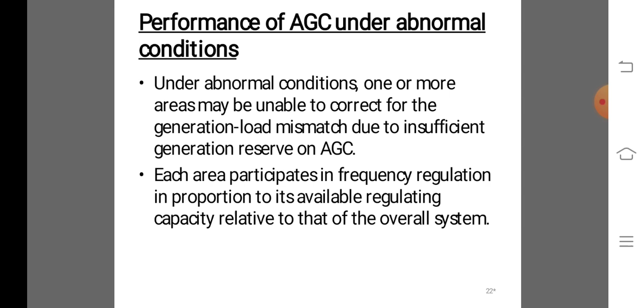Next, frequency bias control. In this frequency bias control, while the initial governor response is the same as for the previous case, the action of the controller in B will force the generation in area B to absorb the load increment in area A.